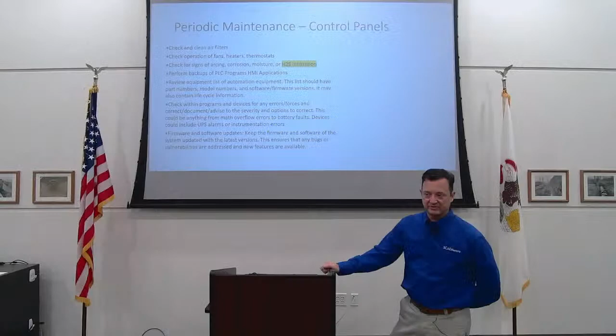You can get hydrogen sulfide inside panels. I don't know how many of you have dealt with it, but I've had entire systems fail because of hydrogen sulfide. The indicator, if you don't know this, is that anything inside a panel that's copper will turn black. Over time it turns brittle, and it destroys all the electronic components and copper wiring inside the panel. So that's definitely something to watch out for. If you have hydrogen sulfide infiltration, there are corrosion inhibitors you can use, but the best solution is adequate ventilation - so look at how you're ventilating your control cabinets.